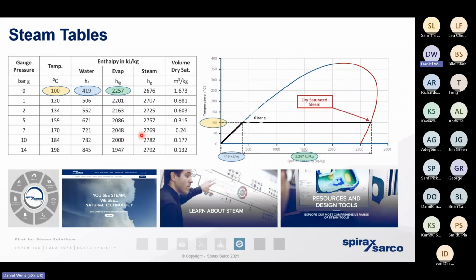And you'll notice there's actually more total heat in steam, and it exists at a higher temperature, at a higher pressure, but there's more energy in the steam at a lower pressure. So for that reason, I encourage you, please don't confuse the issue of temperature with the issue of energy. They're two completely different concepts. And of course, moving across to the opposite side of the screen, the temperature enthalpy curve really plots the journey that water takes as it boils off and changes state to steam in the boiler. But it will only do so when it's got the appropriate energy content.